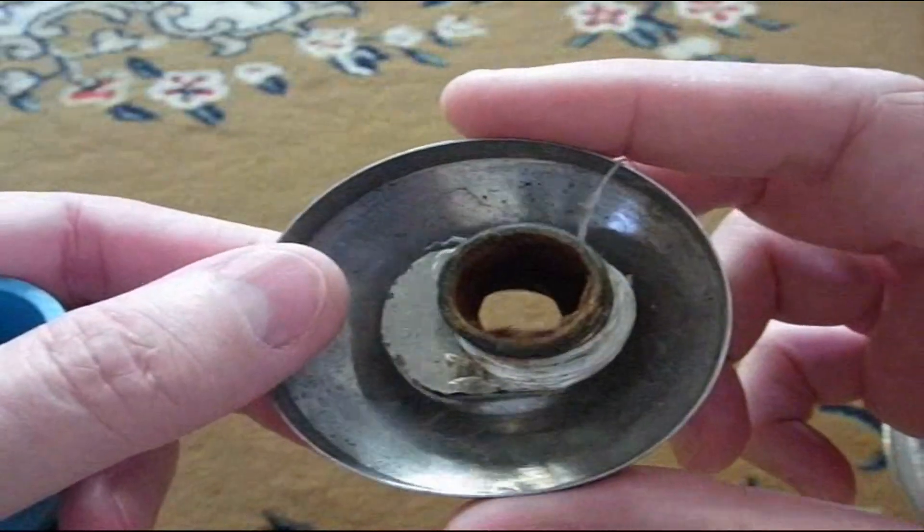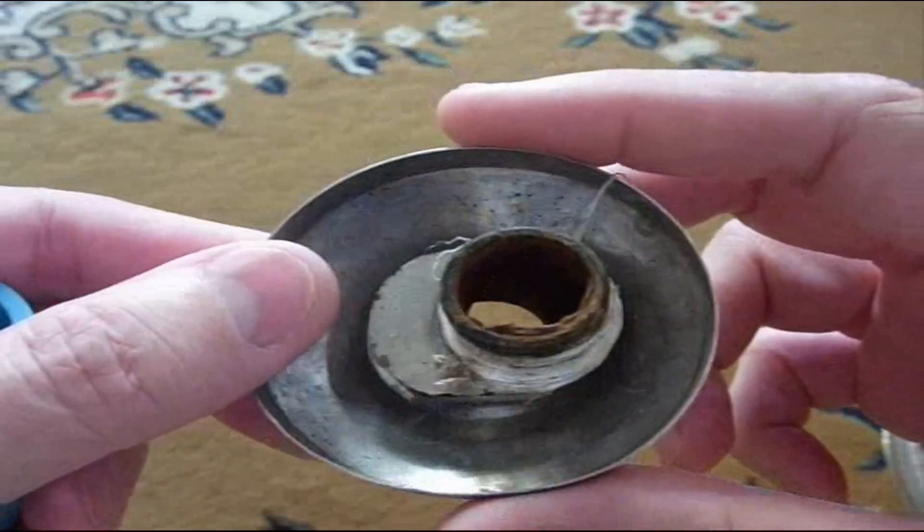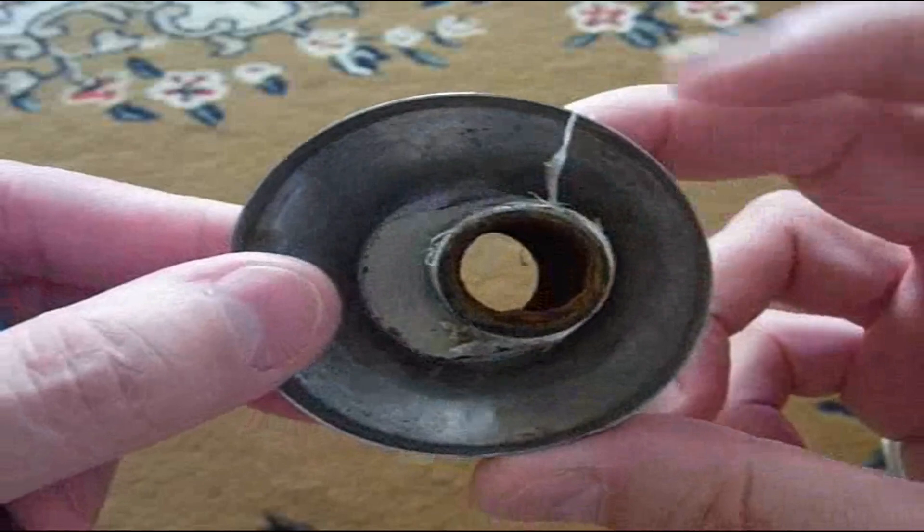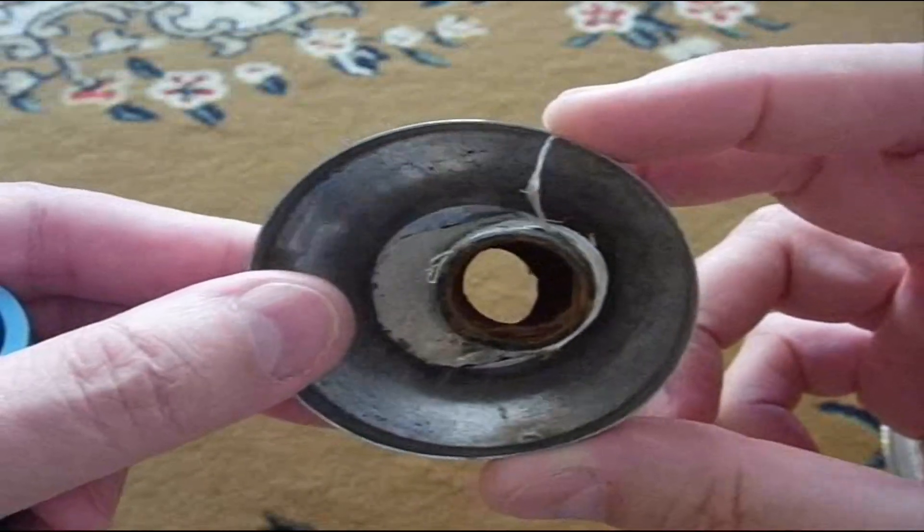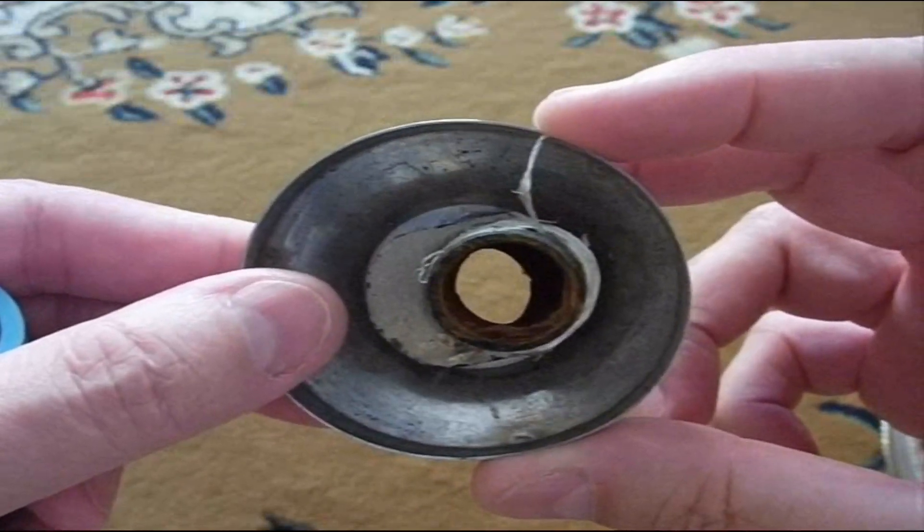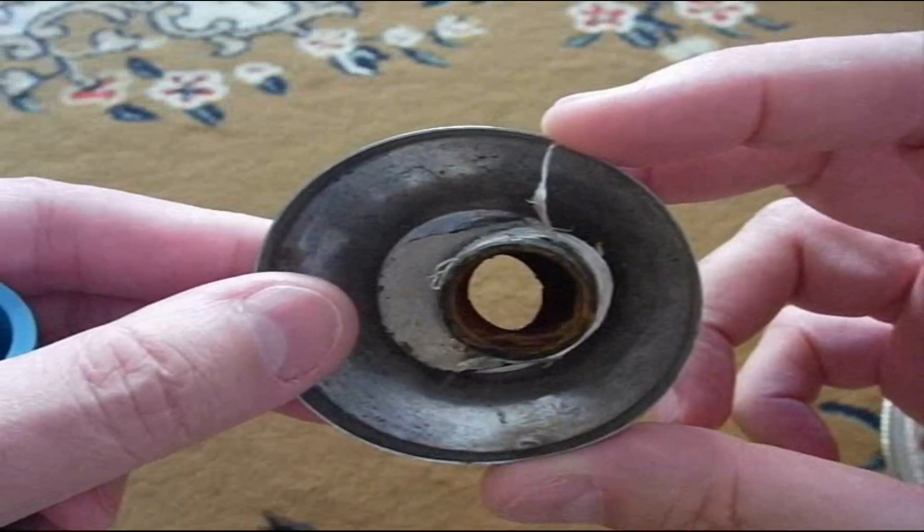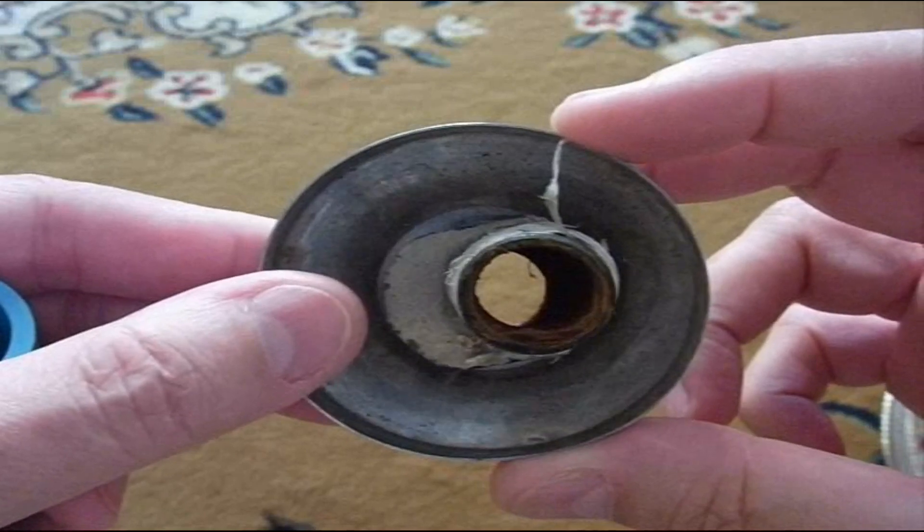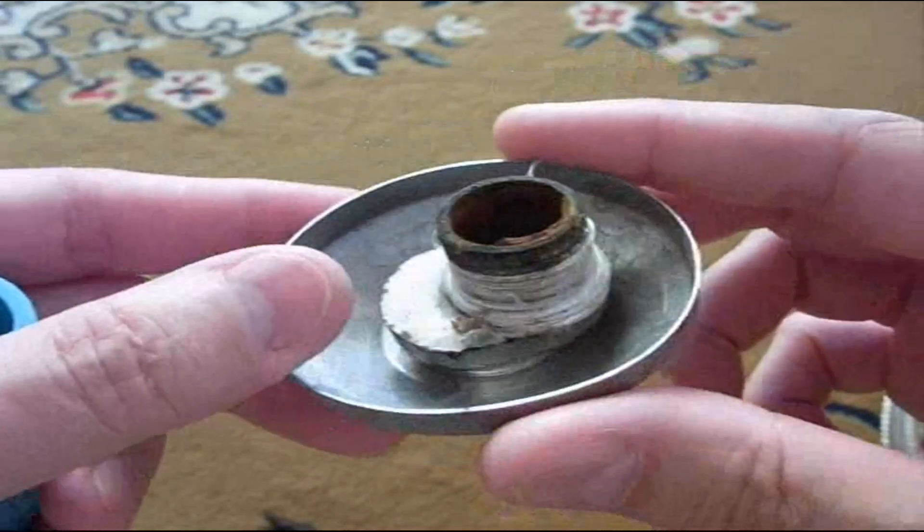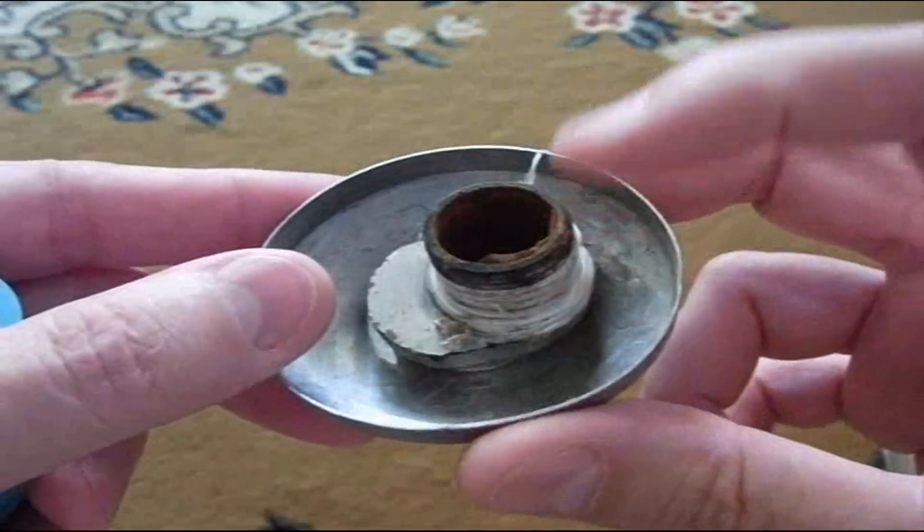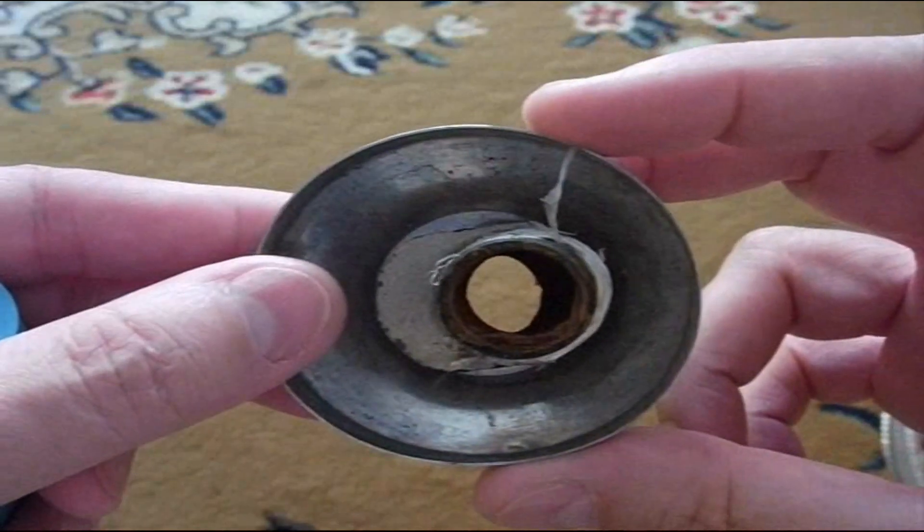Another case. This one's not as bad as another one I found. I threw the other one away. But you can see it starts to get blocked up. And yeah, you can find things like this. So one bathroom is okay, another one is not. The pressure is the same in both, but as soon as you open the dynamic pressure, measure the dynamic pressure, you find out which ones are starting to block up.